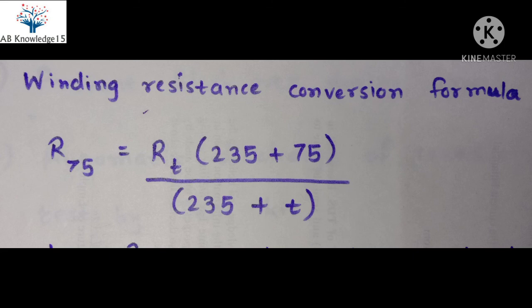From this equation we also conclude that we should note down the winding temperature during the transformer winding resistance test, so that we can convert this temperature and resistance to the standard temperature resistance. So this formula is useful to compare the test results with other temperature levels.